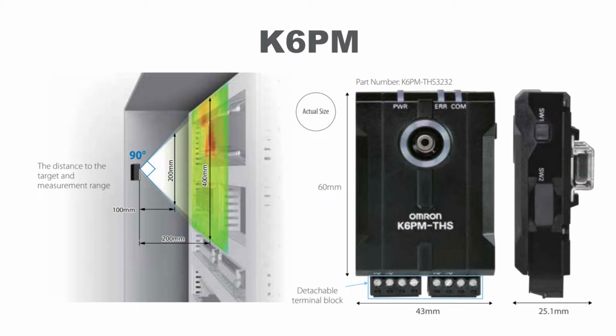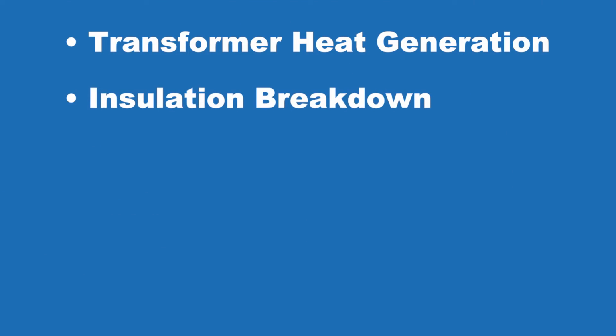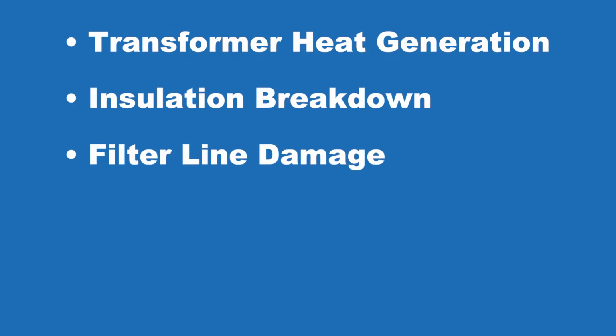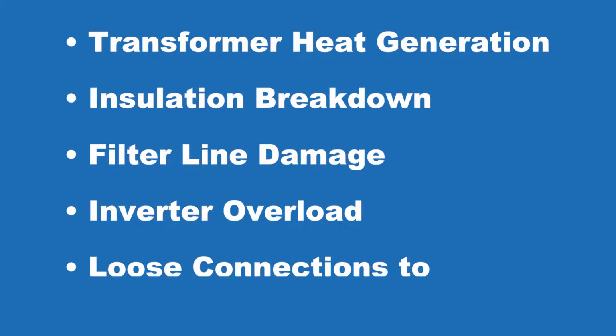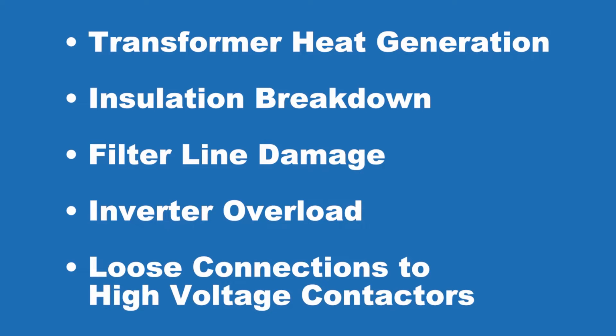Next in our predictive maintenance lineup is the K6PM, a thermal condition monitor. The number of devices in your typical control panel has increased significantly over the years, and at the same time, it's getting harder and harder for plant managers to find and keep maintenance personnel. This means it's all too common for components to fail. Failures like transformer heat generation, insulation breakdown, filter line damage, inverter overload, and loose connections to high voltage contactors can be costly and dangerous. Our solution to this dilemma is the K6PM.